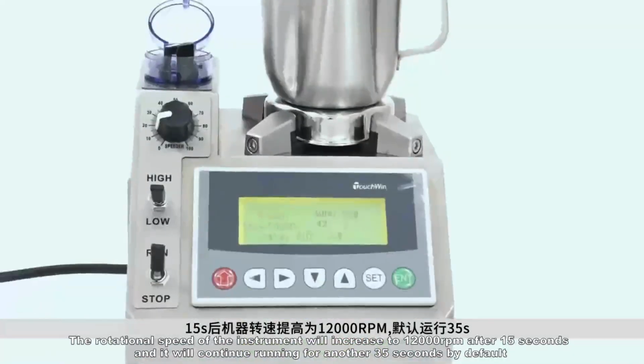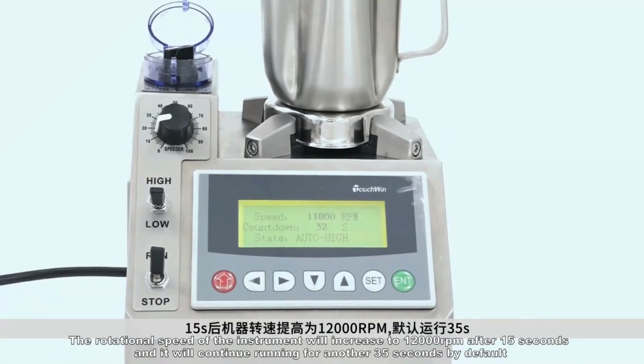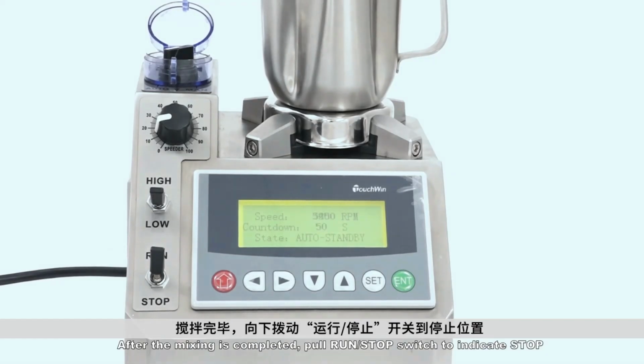The rotational speed of the instrument will increase to 12,000 RPM after 15 seconds, and it will continue running for another 35 seconds by default. After the mixing is completed, pull the run or stop switch to indicate stop.